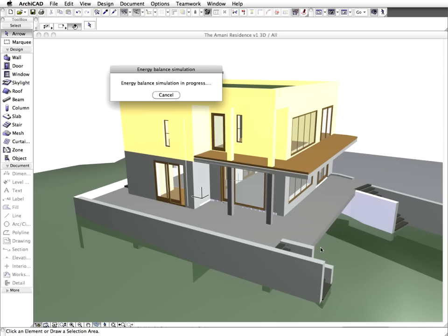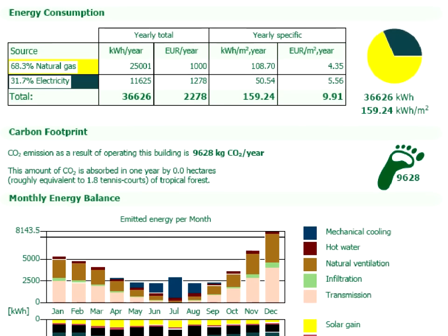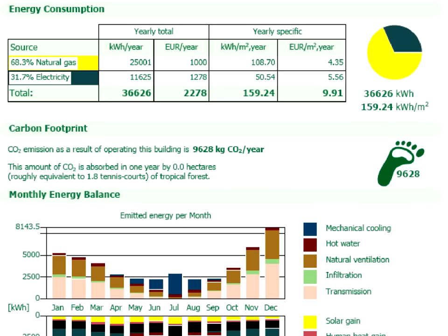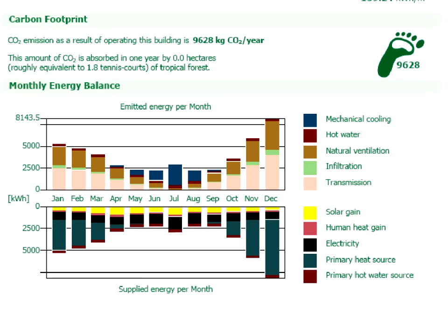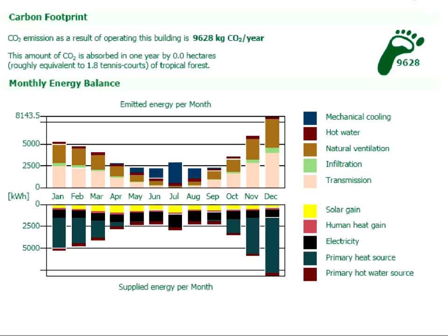Let's start the evaluation again. The Energy Balance Sheet will be displayed in seconds. Notice the huge difference in energy consumption of the building. Both the annual and the specific energy consumption have been reduced by more than 30%. The carbon footprint has also been reduced from 13,000 to close to 10,000 kg of CO2 per year. All of this enormous difference is due solely to the improvement of the thermal properties of the two building structures. Improving the thermal properties of the openings can also cause similar significant improvements in the energy balance of the building.